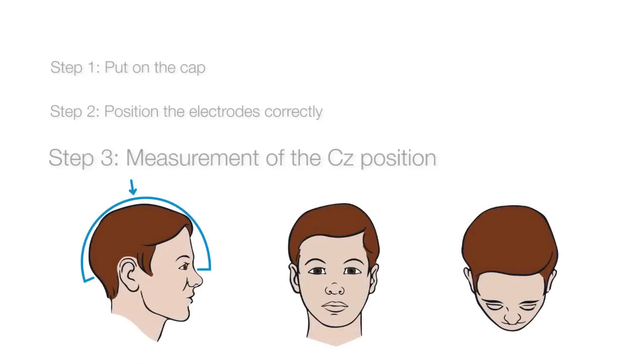Take the point halfway between the nasion and inion and the point halfway between the two pre-auricular points. The vertex electrode, Cz, is positioned where these two points meet.